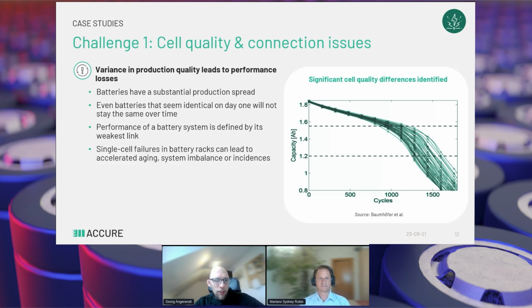This means batteries won't stay the same over time, which is critical because the performance of a battery system is defined by its weakest link. Even with many good cells, one bad cell could reduce the performance of the entire system. Single cell failures in battery racks can lead to accelerated aging, system imbalances, or incidents. This is also why even the best trained battery models are not 100% accurate, because you cannot measure all the outliers.